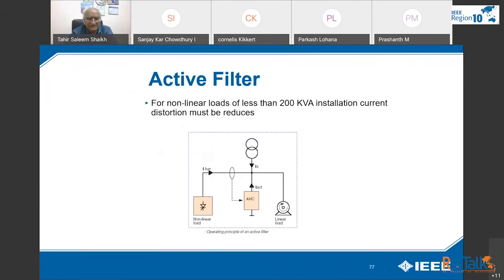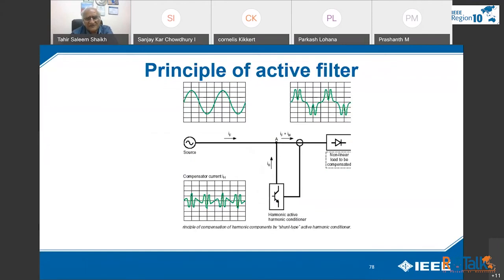Active filter. Active and hybrid filters are very expensive. They are for non-linear loads of less than 200 kVA, where current distortion must be reduced. The simple idea is that a non-linear load of the 3rd, 5th, 7th, 11th harmonic type, whatever it may be, generates harmonics. A counter in opposite phase, this harmonic generation unit creates a harmonic level which nullifies the impact on one phase, second and cross phase, and gives a simple noise-free sinusoidal waveform to the linear loads. So this is called an active filter or sine filter also. This is very expensive. In principle, these are the simple waveforms over here.